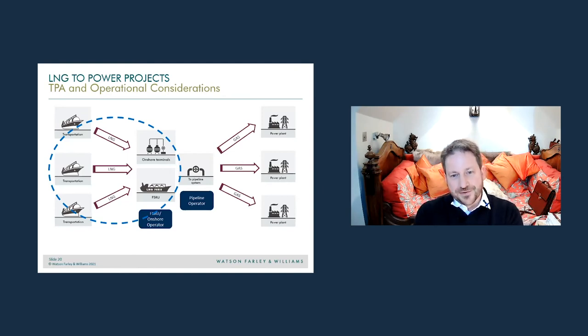And of course, when I mentioned the fleet that was mostly going to be delivering, all of those vessels, essentially, post 2006 onwards, would have been built with the membrane containment systems. And so in those open water FSRU locations, they have the added issue that they must not put to sea, if you like, pull out of the transfer, while the liquid levels are within the sloshing limits.